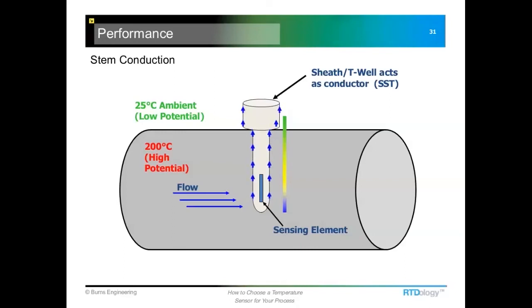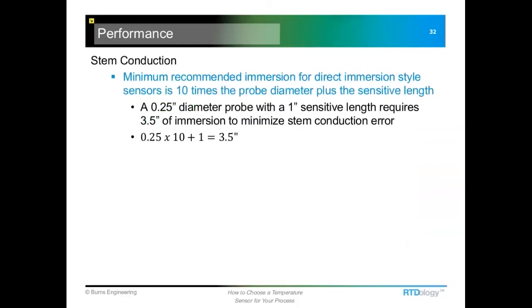With our example here, if we were to look at something like this with a 2.5-inch immersion, and it's 200 degrees C in the process and 25 C for ambient, here we'd probably have maybe like a 3 degrees C error. And it's just kind of a guess, but that could very easily be the reality. And so that kind of makes our initial 0.3 degrees C temperature probe just look very inaccurate.